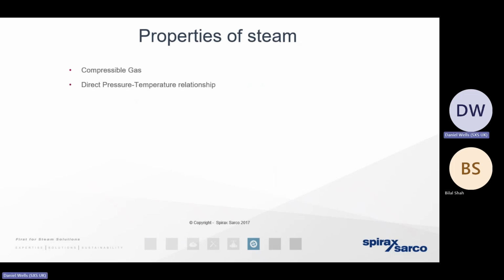One of the fundamentals that sets steam aside from hot water is the fact that steam's got a pressure-temperature relationship. If we know the pressure of the steam, we know its temperature. If we need to achieve a particular temperature at a process, we can bring that around very, very easily by a very, very simple set of controls. Typically, it's a pressure reducing valve. We know the pressure, we've controlled the temperature. But it also tells us that we need a really good number of pressure gauges around a steam distribution network. Without those pressure gauges, we've got no understanding of what we're working with.